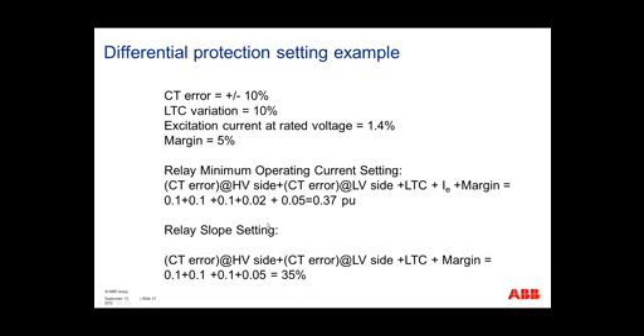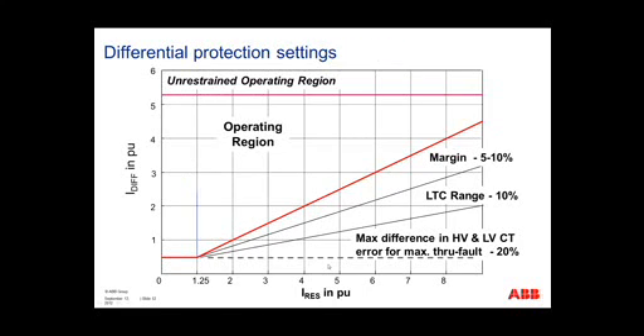With these errors in mind, we can calculate our slope setting. Slope setting is set after 1 per unit. We will see that we'll have about a 35% slope. And with this 35% slope, we take into account that the higher current in the restraint coil will give us more of an error in our differential protection. So our errors are accounted for, shown here on the right.